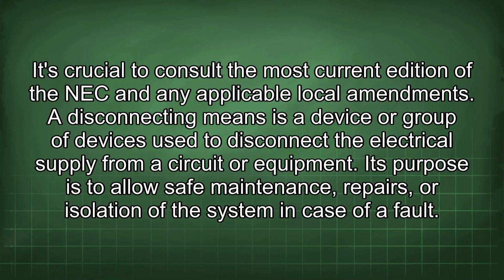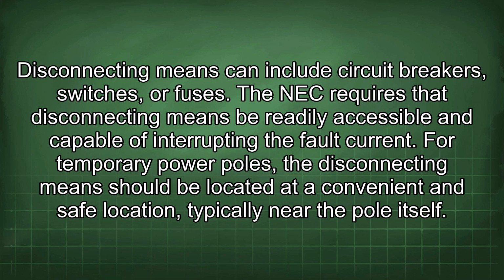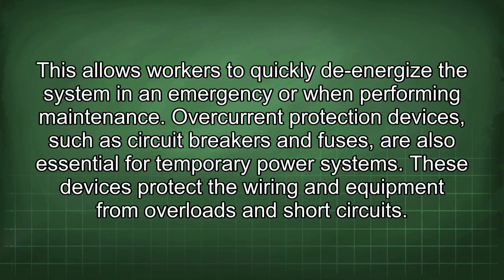A disconnecting means is a device or group of devices used to disconnect the electrical supply from a circuit or equipment. Its purpose is to allow safe maintenance, repairs, or isolation of the system in case of a fault. Disconnecting means can include circuit breakers, switches, or fuses. The NEC requires that disconnecting means be readily accessible and capable of interrupting the fault current. For temporary power poles, the disconnecting means should be located at a convenient and safe location, typically near the pole itself. This allows workers to quickly de-energize the system in an emergency or when performing maintenance.